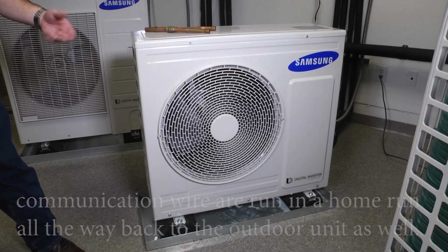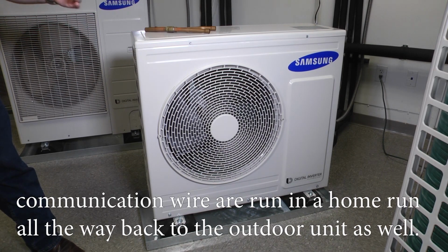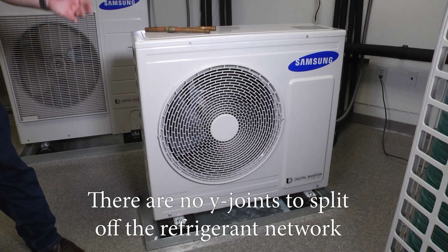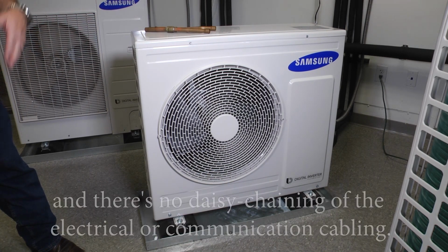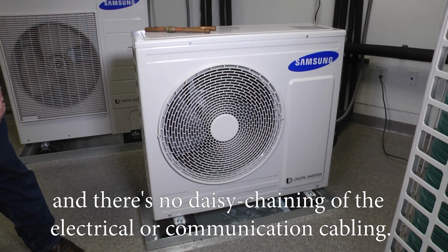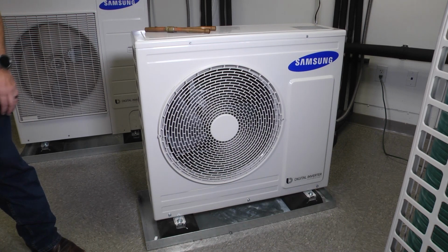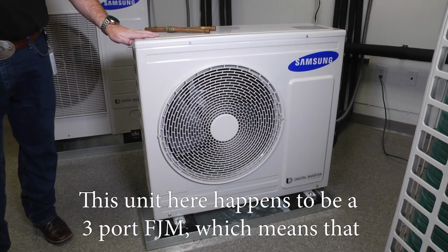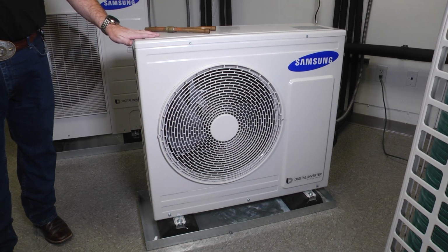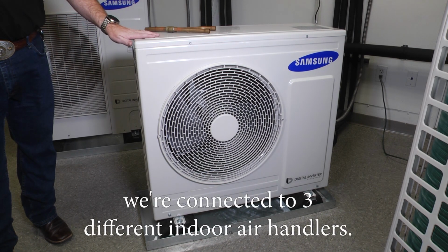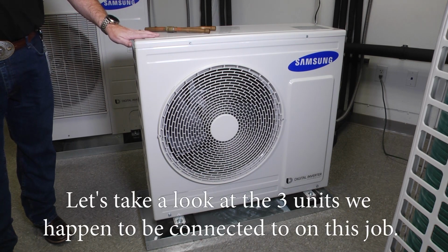and the high voltage and the communication wire is run in a home run all the way back to the outdoor unit as well. There's no y-joints to split off the refrigerant network, and there's no daisy chaining of the electrical or communication cabling. This unit here happens to be a 3-port FJM, which means we're connected to 3 different indoor air handlers. Let's take a look at the 3 units we happen to be connected to on this job.